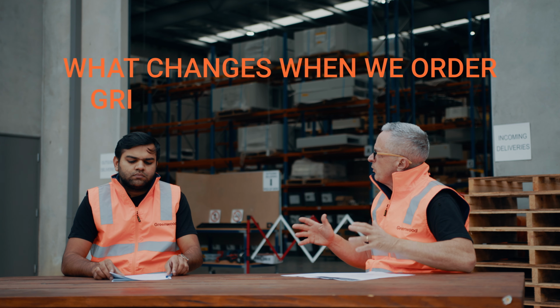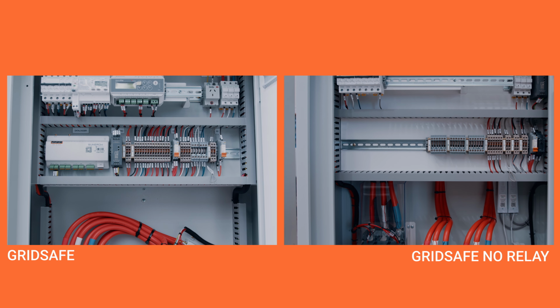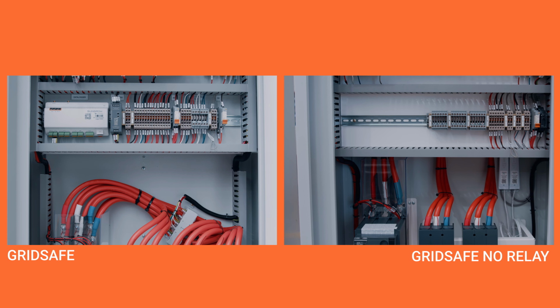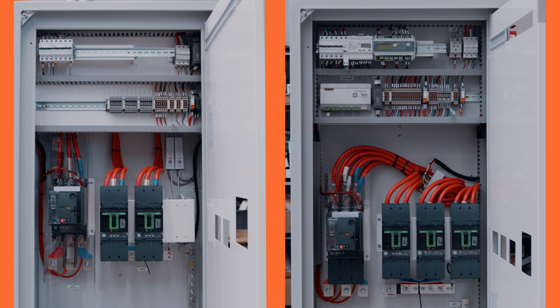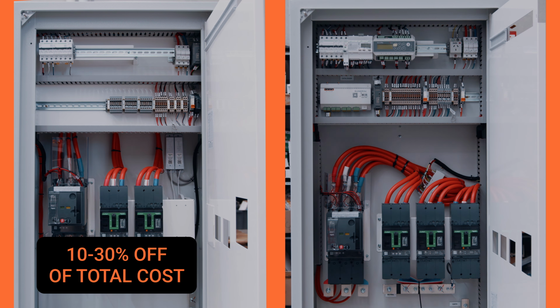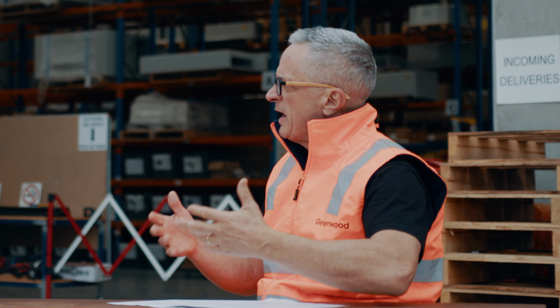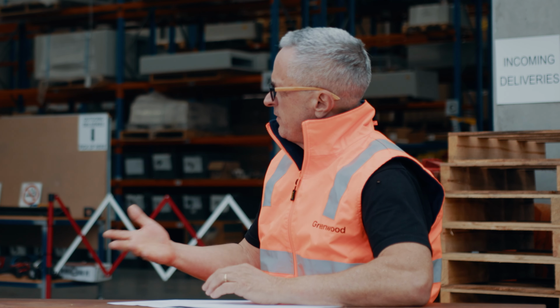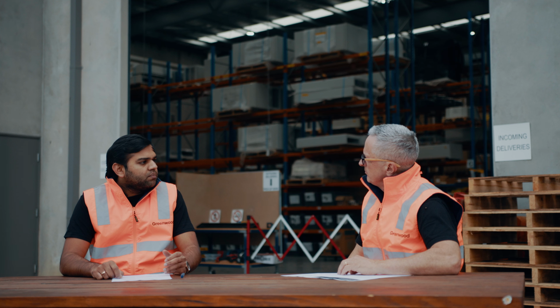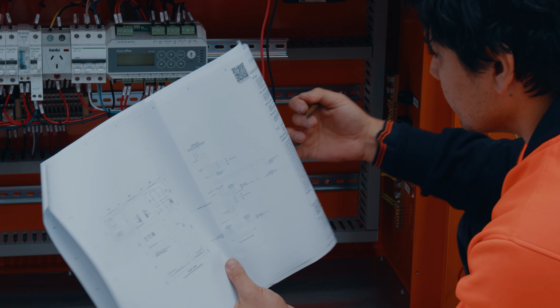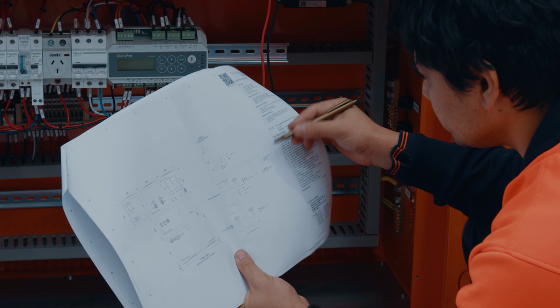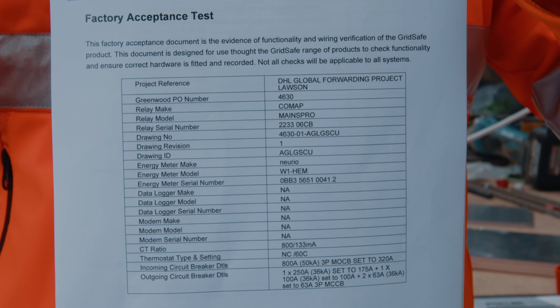What changes when you order a GridSafe without a relay? If the customer orders the GridSafe without a relay, it would be the same enclosure and the circuit breakers. The only change would be there won't be an interface protection relay if it is not required, and there might be some cost difference of maybe around 10 to 30% of the total cost. Without a relay, the enclosure still remains the same from the perspective of being certified and type tested. Exactly, that's correct, because even if the interface protection relay is not present, the enclosure needs to be type tested to AS 61439 for that purpose.